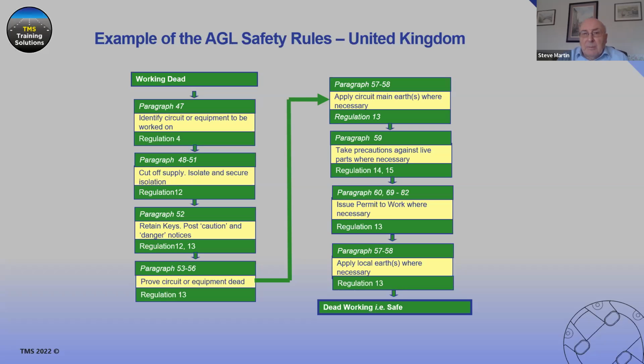Once that's done, we want to earth the circuit, because even if we've got the right circuit isolated, we may have other cables or circuits running adjacent, and we can get induced voltages of 100 to 150 volts easily on our circuit if we don't earth it down. We have long runs of cable, several kilometers, which can pick up these induced voltages.